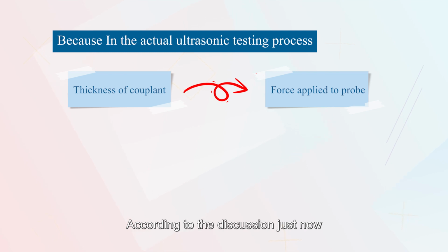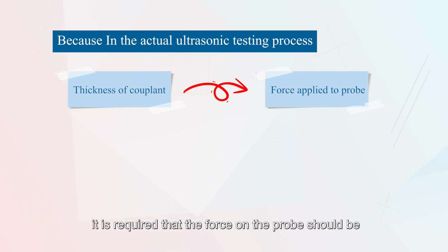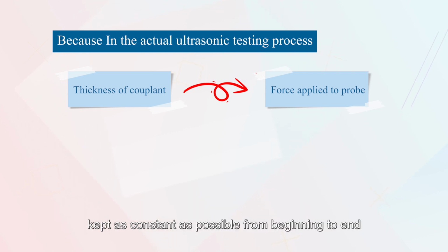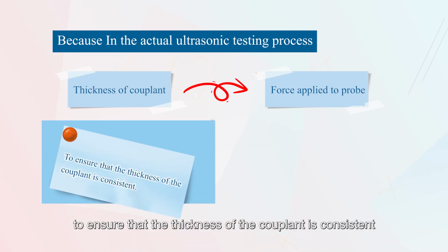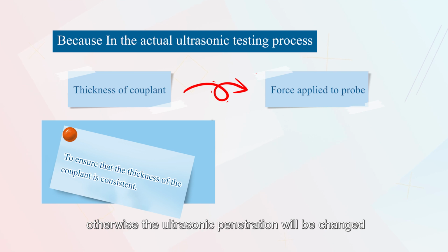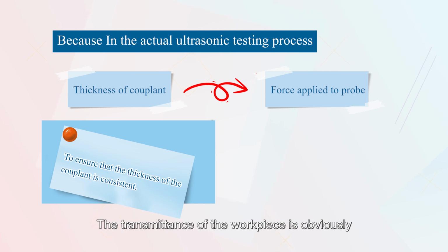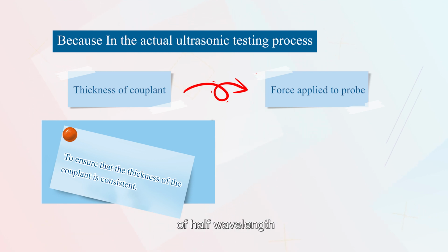According to the discussion just now, it is required that the force on the probe should be kept as constant as possible from beginning to end, to ensure that the thickness of the couplant is consistent. Otherwise, the ultrasonic penetration will be changed. The transmittance of the workpiece is obviously difficult to achieve in manual inspection, let alone guaranteed to be an integer multiple of half wavelengths.